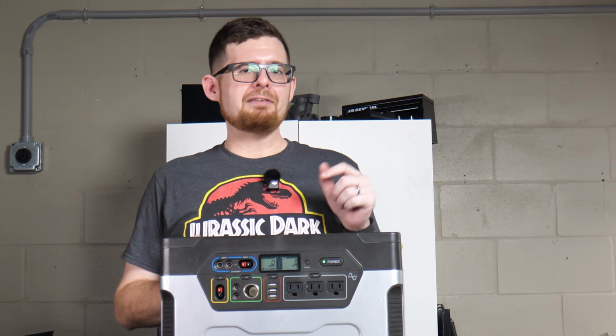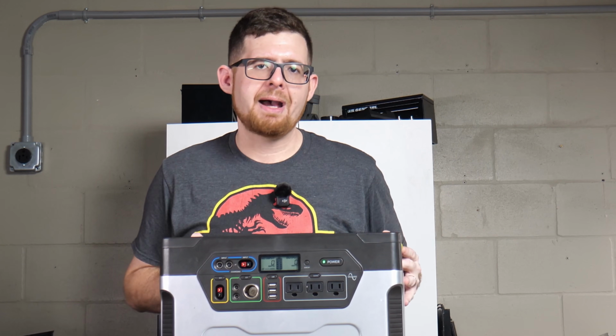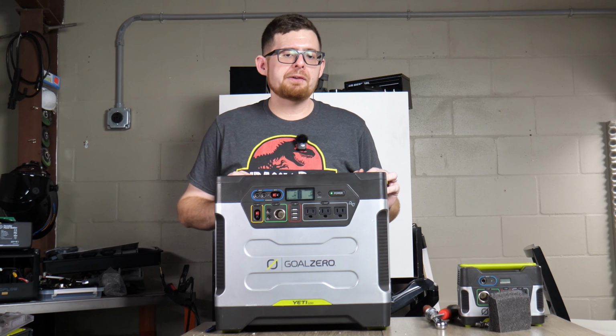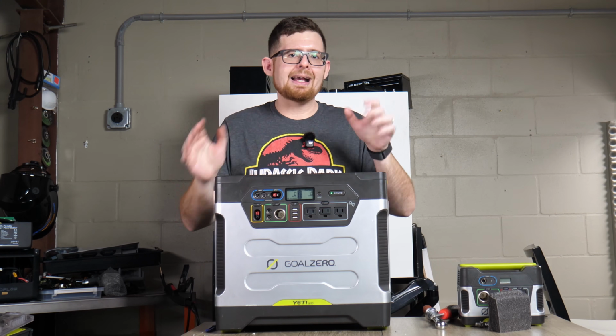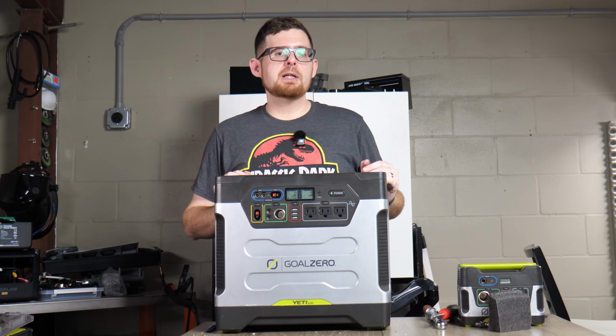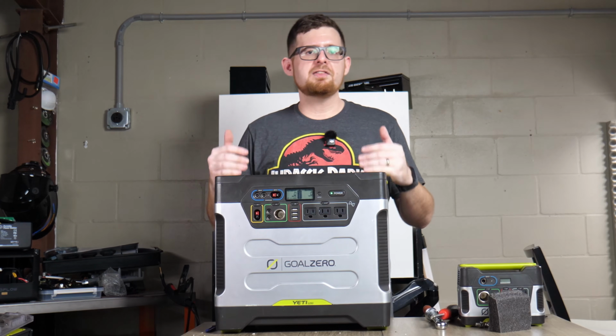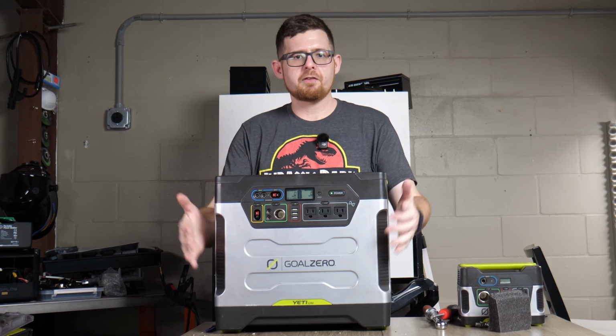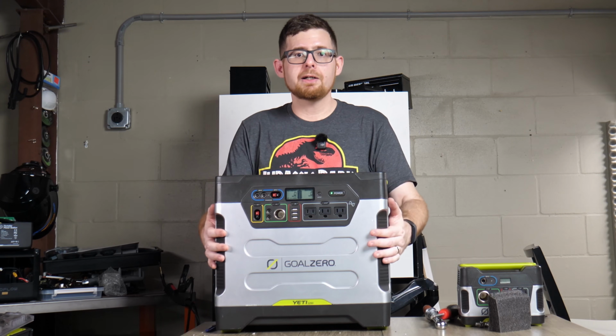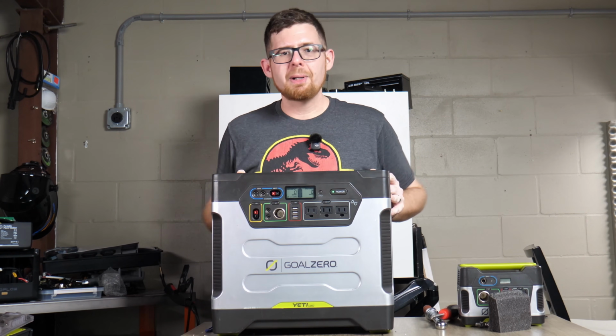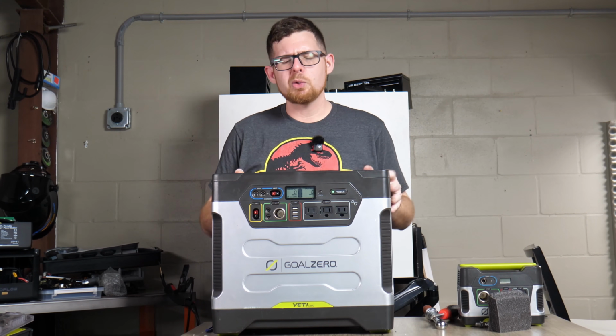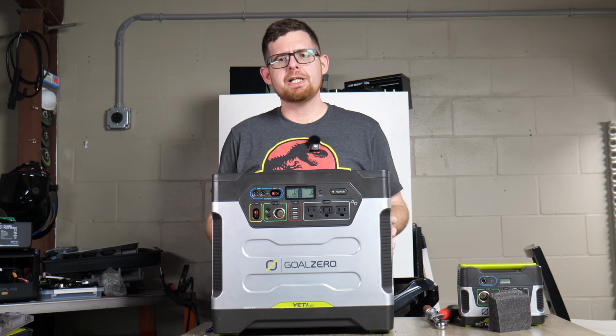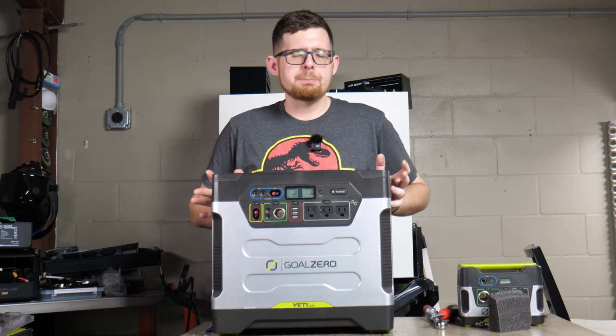So that's one thing to keep in mind when using this kind of battery in this kind of unit. Functionality-wise, this should perform exactly as advertised. The battery inside can put out up to 100 amps continuous, which is more than sufficient to supply the 1250 inverter in here, even at full load, which is around 1400 watts DC, enough to supply the inverter even with its about 80% efficiency.